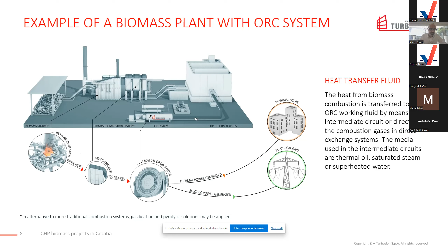I'm here, as I told you, for biomass. This is an example of a biomass plant with an ORC system. On the left side you see the biomass stock, and in the central part there's a combustion system. Traditionally it's combustion, but we have also developed projects with gasification and pyrolysis, which could be a new step for innovation combining ORC with these technologies. Then the ORC heat exchanger transmits the thermal power to the diathermic oil, which allows the ORC system to generate power for the grid and heat for the thermal user in a closed loop.